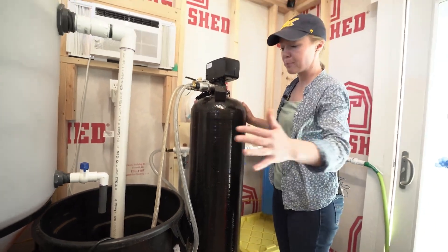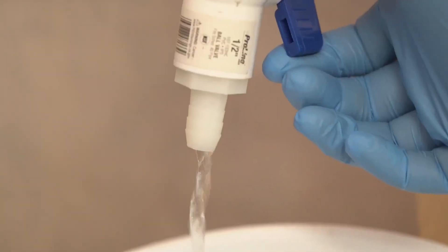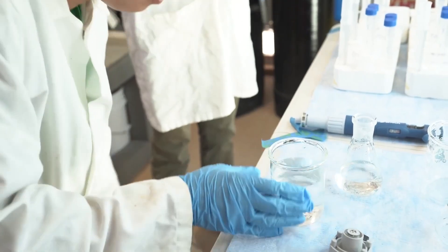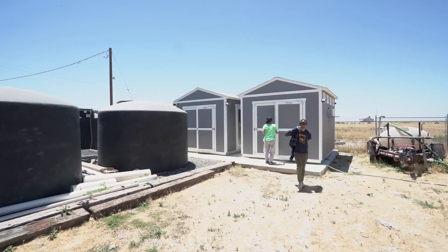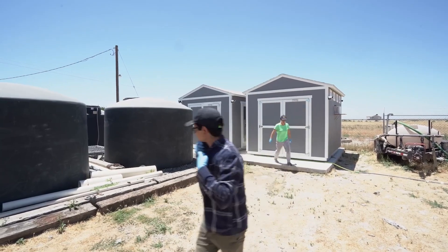The water gets pushed through this sand filter to remove bigger particles that have escaped. Then we have the micron filters. We take samples every hour to check on arsenic concentrations. The influent groundwater has about 200 parts per billion arsenic. By the time we've treated this water, it's coming out consistently below 10 parts per billion. This promises to be one of the lowest, if not the lowest cost, ways to reliably remove arsenic from groundwater at a price that local communities can afford.